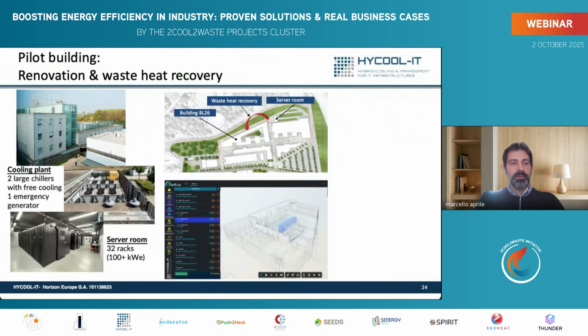It's a pilot building undergoing renovation, including a waste heat recovery system. We are following a big renovation project that involves renovation of a server room using a more effective heat exchanger for cooling, meaning we can work with higher temperatures of chilled water. There's also renovation of the cooling system, meaning we can use better free cooling and increase efficiency at partial load operation. We're also renovating the building itself to limit the heat demand in winter, especially the peak.